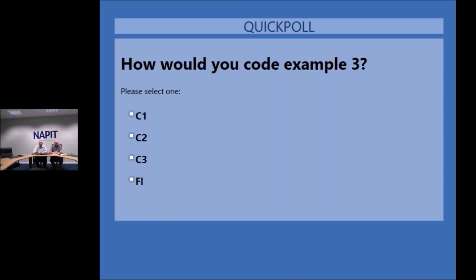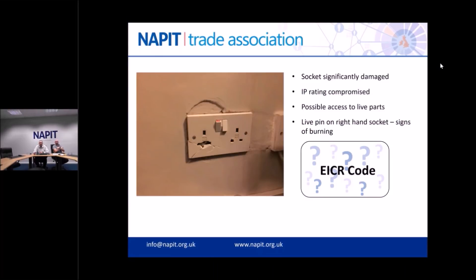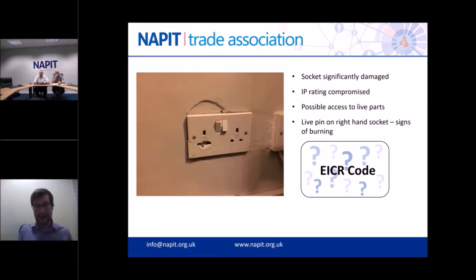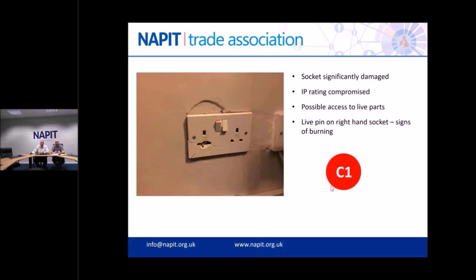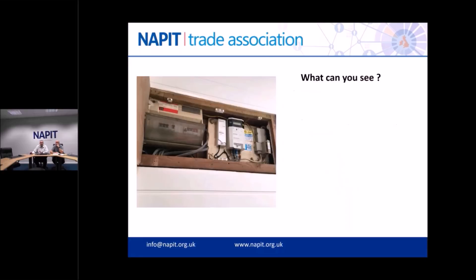The fourth image shows a socket that's completely smashed - IP rating compromised, possible access to live parts, and the live pin on the right-hand side showing signs of burning and thermal damage from taking a significant load. Poll: 97% correctly coded this as C1. Absolutely right - there's access to live parts; you can put a finger, probe, or prod in there. If you can see it and touch it, it'll kill you now - that's an immediate C1.